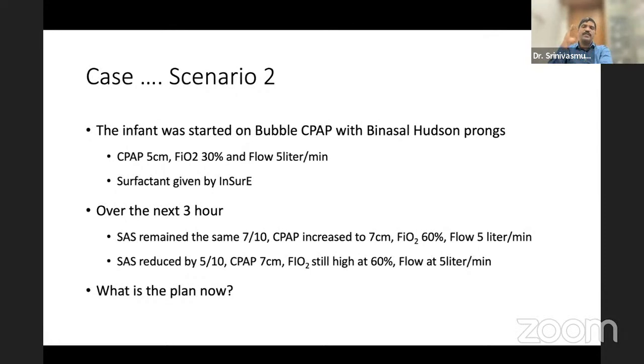How do you know that the flow is adequate? There should be continuous bubbling, flow of 5. If the flow is not adequate, look for leaks, correct the leaks and increase the flow. If still bubbles are not there, probably there is a leak around the nostrils. If bubbles are there, auscultate, and if bubbles are heard, yes, the pressure is reaching the lungs. Bubbles seen, but bubbles are not heard, that means the pressure is there in the circuit but not reaching the lung. Probably there is some obstruction in the nostrils. So you open up the nostrils, clean the nostrils, add some saline drops, and then you auscultate and see. And if the bubbles are reaching the lungs, you will be able to hear the bubble sound.